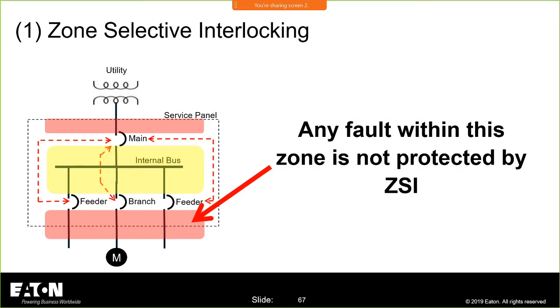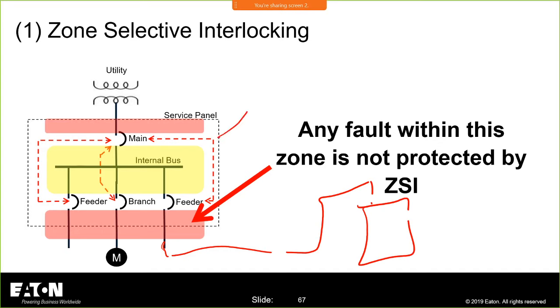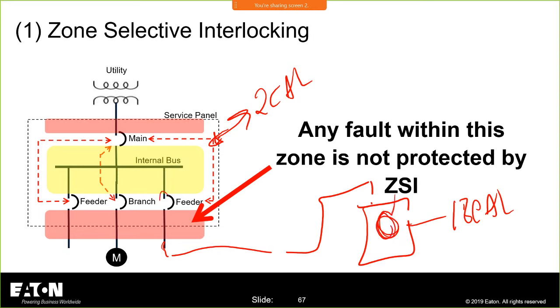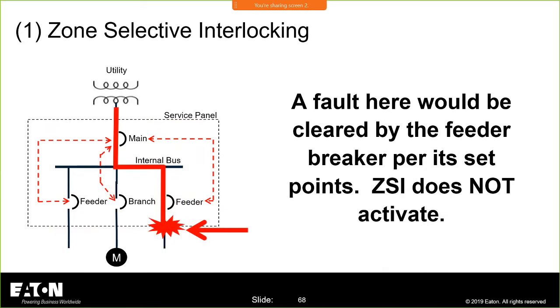So if this feed is supplying a panel board, and you look at this arc flash energy inside of this equipment, it says this is 2 calories, and you're looking at this one and it says it's 18 calories, and you go, well, wait a second, I have an arc reduction technology up here in my main equipment. How can it be greater? It's because you're basing the clearing time off of that feeder breaker and your lower fault current, so you're not getting protection from the zone selective interlocking. So that's basically what these next slides tell you.